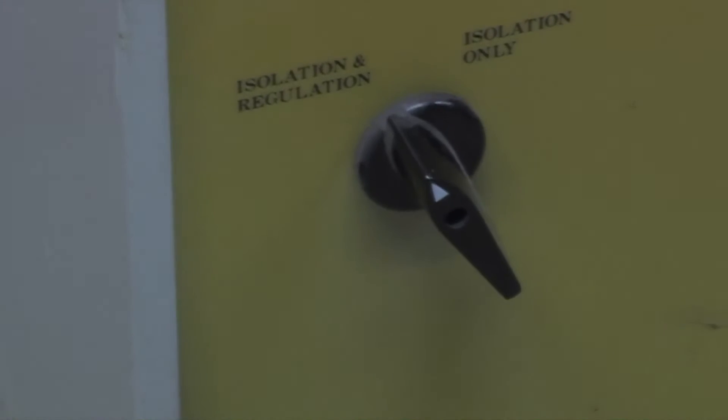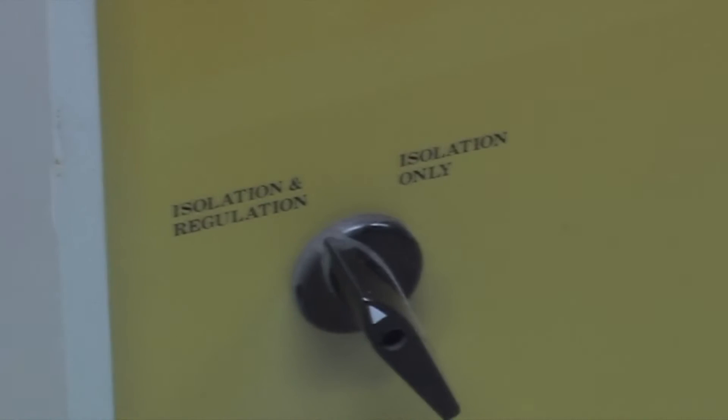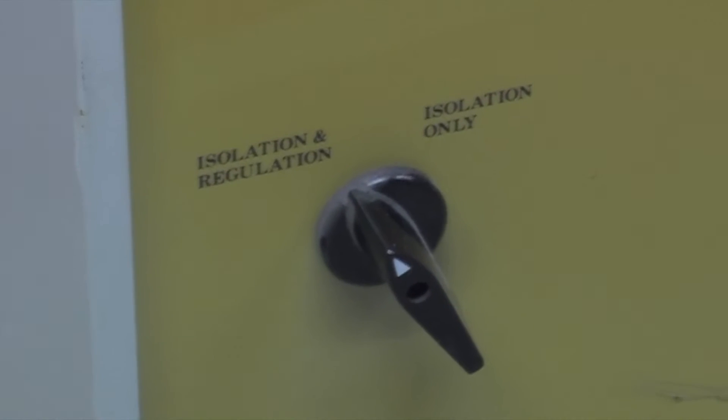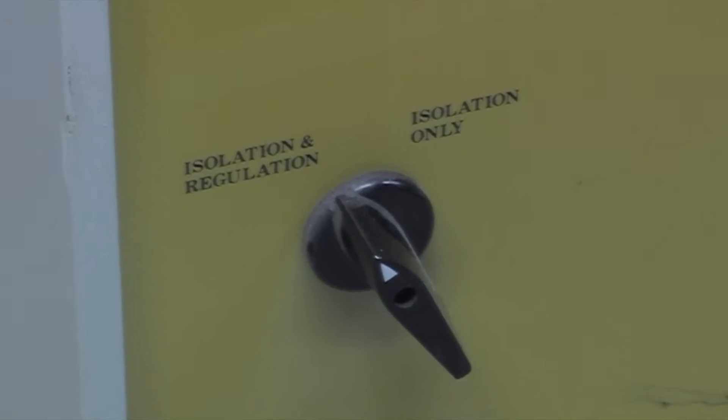On the front we have a switch for isolation and regulation, or isolation only mode. The isolation and regulation mode also means it's soft start, so instead of having a big inrush as soon as you knock it on and tripping the breaker, it warms itself up gradually — a nice gentle start up.